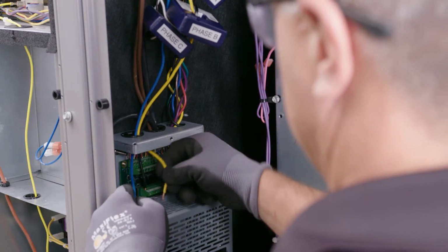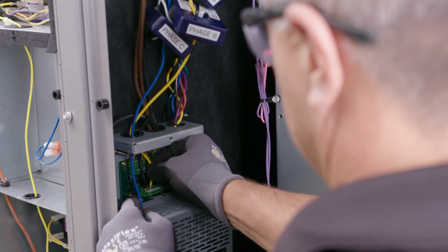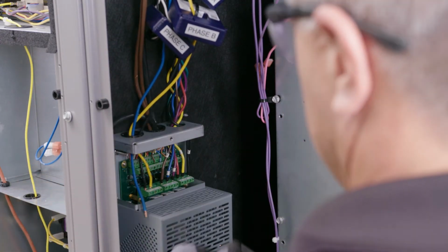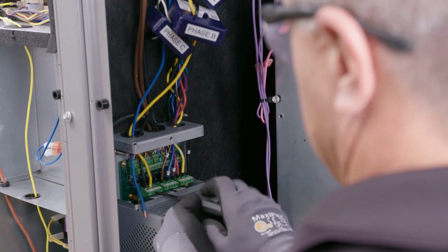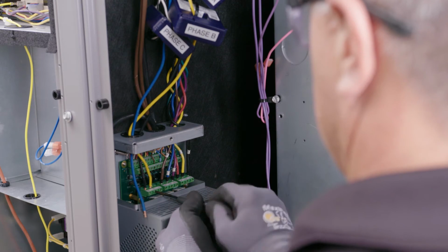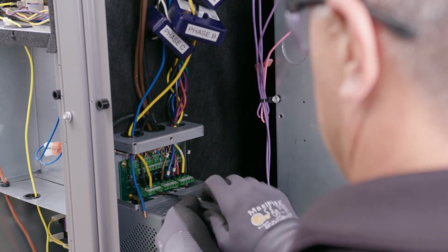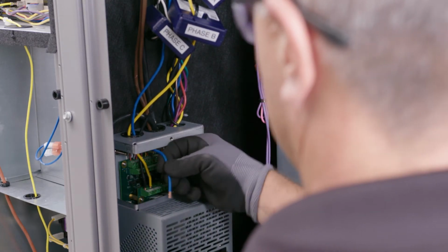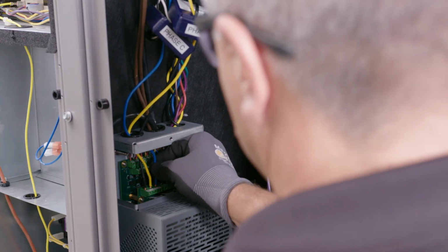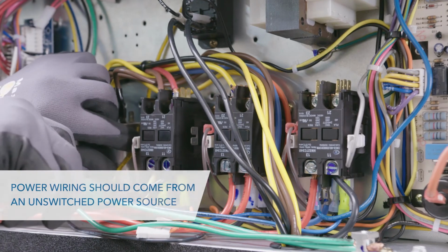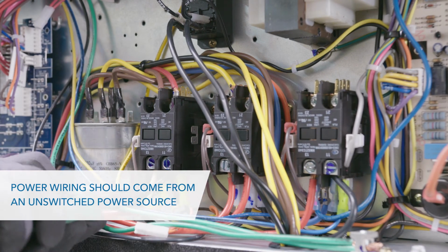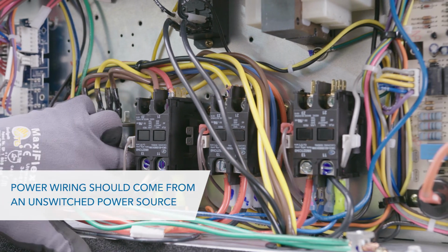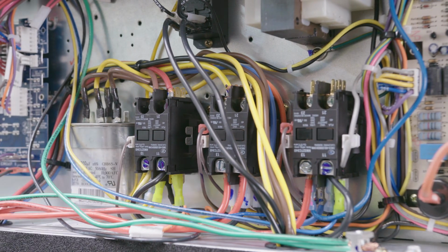Now we're going to install the line voltage, which can be connected to any phase in any order to power the device. You may be able to reuse the power wiring from the old motor and connect it to the input of the motor controller. Reference the RTU and wiring schematics for correct wiring. It is preferred that the power wiring come from an unswitched power source. This may require moving the power leads from the load side to the line side of the RTU contactor or to another unswitched line power source in the RTU electrical panel.